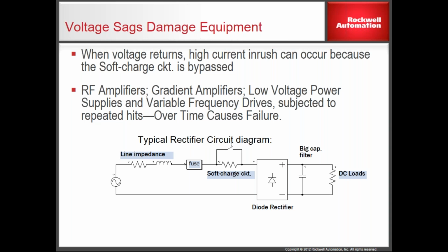Imagine I flip the switch on in this circuit and start to charge the capacitors. Managing that current flow into the diode rectifier circuit is something called a soft charge circuit, which just manages the current flow. When we get about 80% fully charged on the power supply or drive, we close a bypass around the soft charge circuit so we have full access to current when the drive is doing its job, nothing to slow it down.